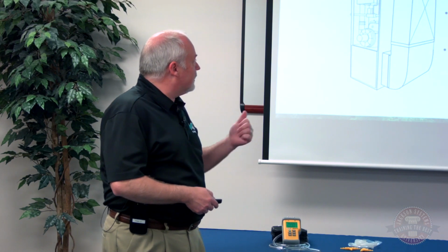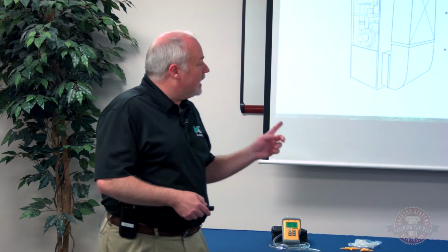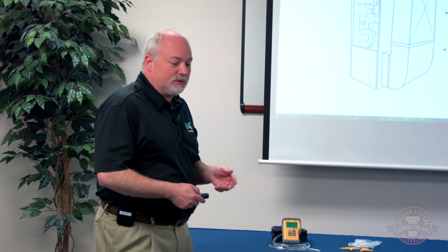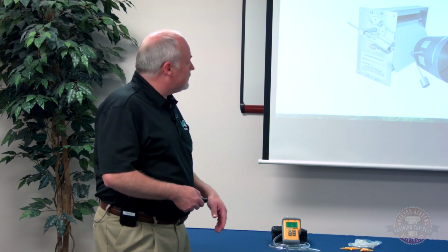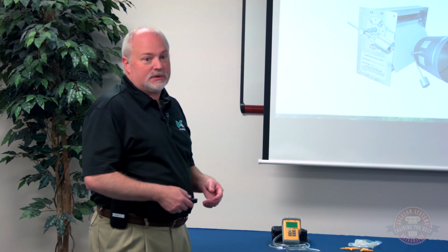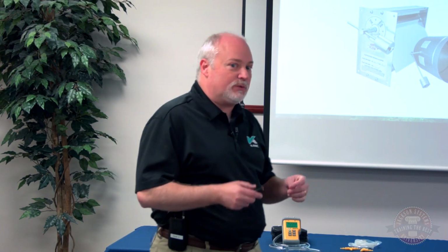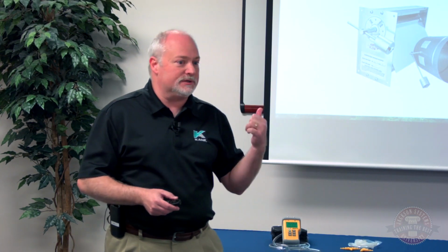Any questions on taking our external static pressure across the different components of our system to find an issue? Well, the last thing we want to look at as far as external static pressure, of course, is zone systems. If you're working on a zone system that has a barometric damper in it, being able to test that so we can adjust and set that damper is a valuable tool.